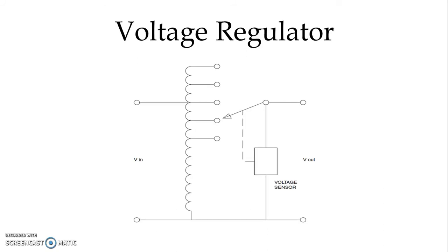In the diagram we can see one voltage regulator, a switching type of voltage regulator. The electronic switch responds to a signal from the voltage sensing circuitry and switches to the tap connection necessary to maintain the output voltage constant. The switching is typically accomplished within half of a cycle, which is within the ride through capability of most sensitive devices. We can observe one voltage sensor here and this switch gives the signal to change the tapping and we can maintain the output constant voltage.